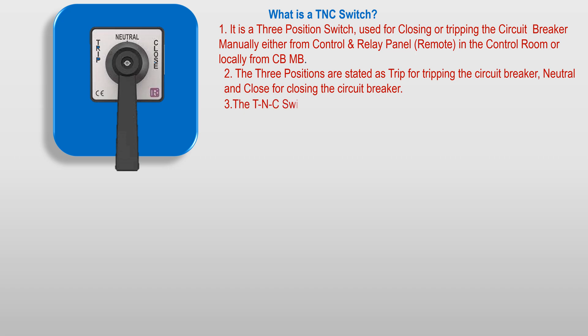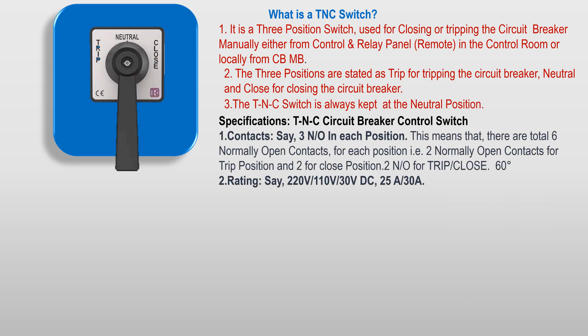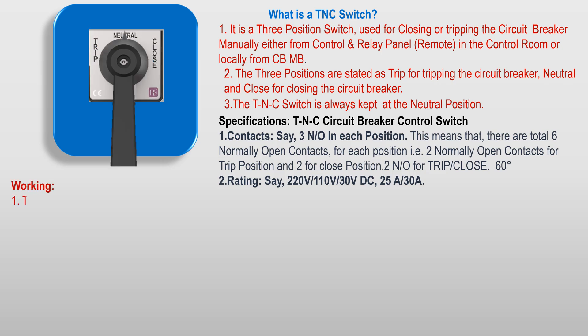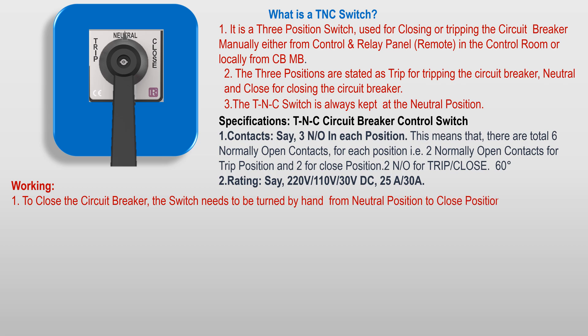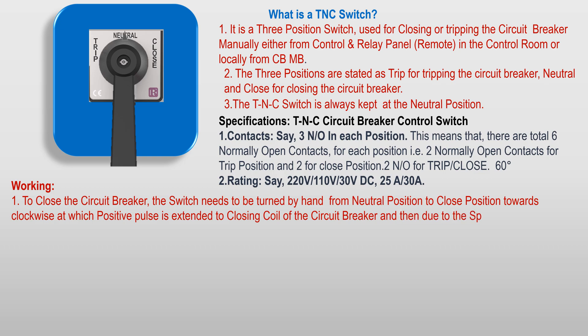The TNC switch is always kept at the neutral position. To close the circuit breaker, the switch needs to be turned by hand from neutral position to closed position in the clockwise direction, at which a positive pulse is sent to the closing coil of the circuit breaker. Then, due to spring action, the switch automatically comes back to the neutral position when the hand is taken off.